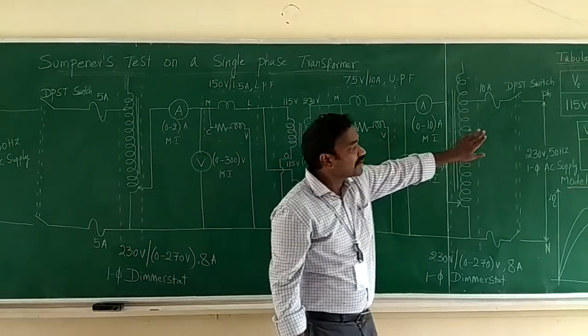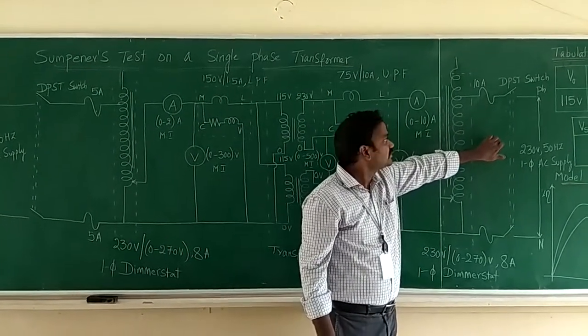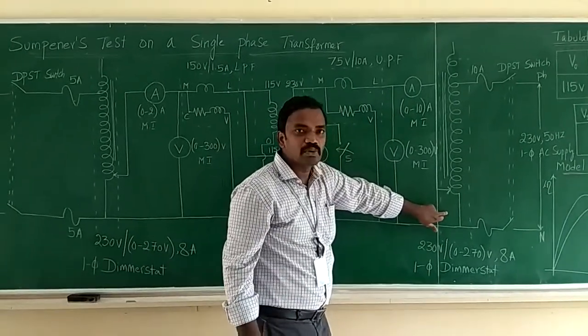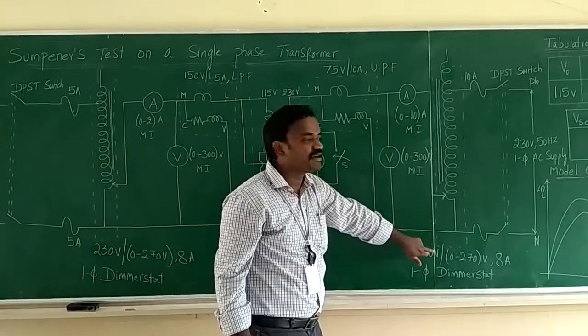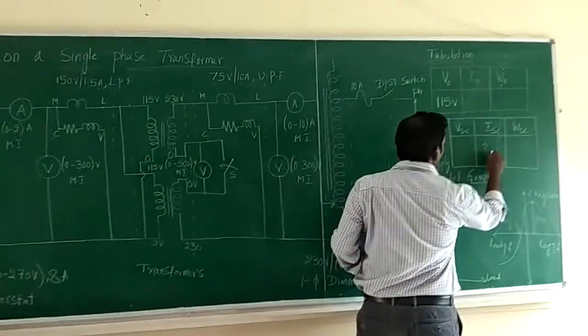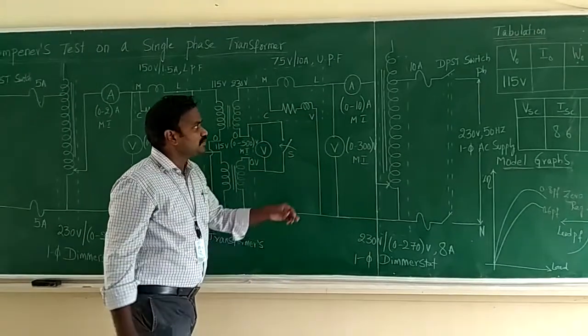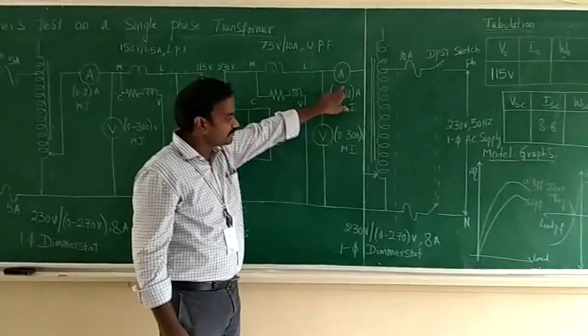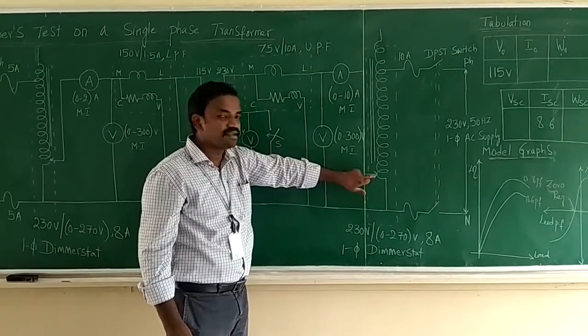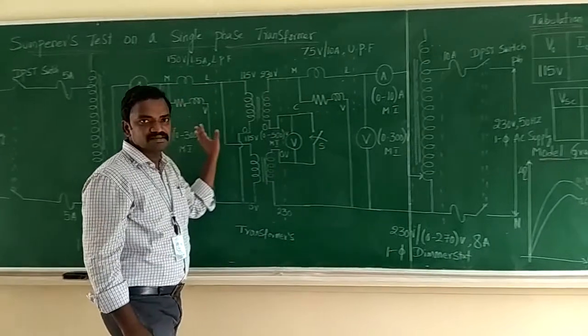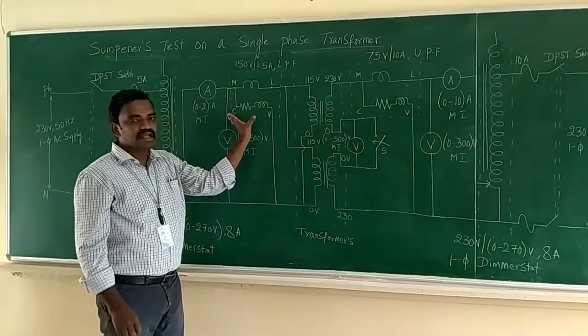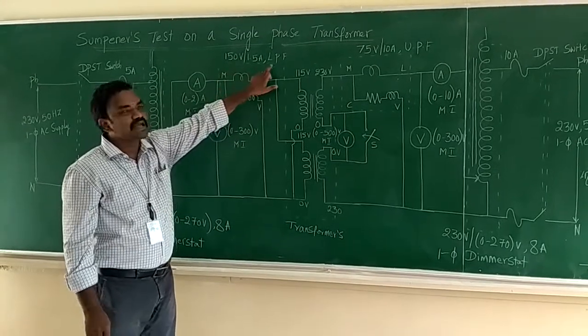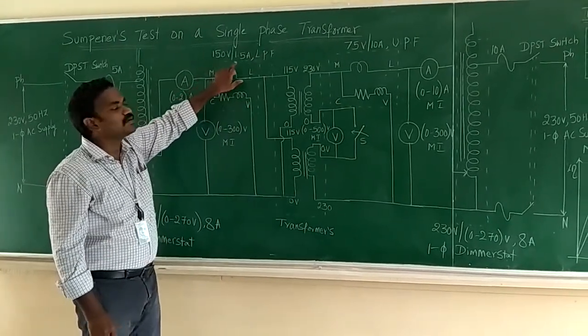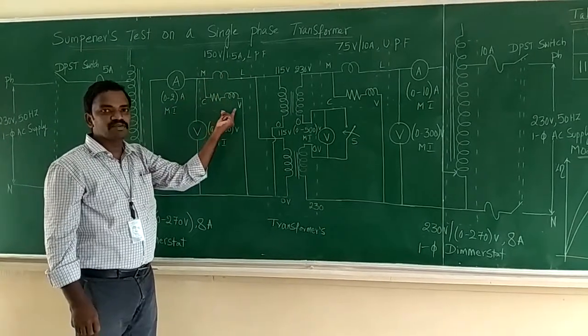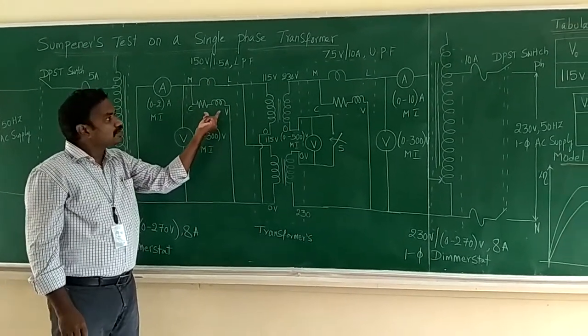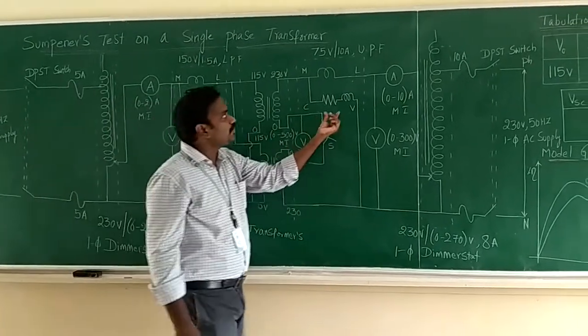Now, by closing the DPST switch at the secondary side and varying the dimmerstat slowly, the rated current has to be applied here. The rated current here is 8.6 amperes. So 8.6 amperes has to flow by slowly varying the dimmerstat or variac, and then we take all the readings. Here the LPF wattmeter, with a range of 150 volts, 1.5 amperes, will show us the core losses, whereas the UPF wattmeter will show us the copper losses.